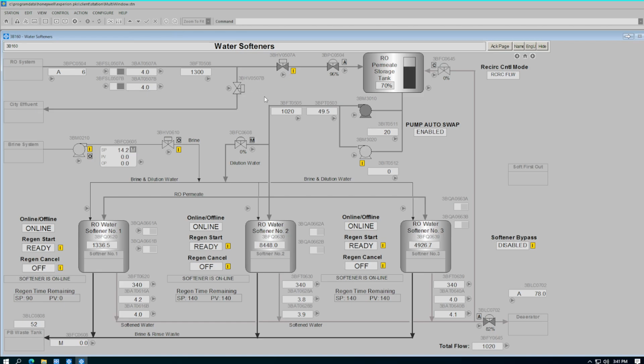You must fix the situation causing the alarm before the operator can switch the valves back to their normal operating positions. You will notice we have an interlock on valve A. This is to prevent you from closing this valve till the other valve has been opened so we don't deadhead the booster pump for the RO skids.